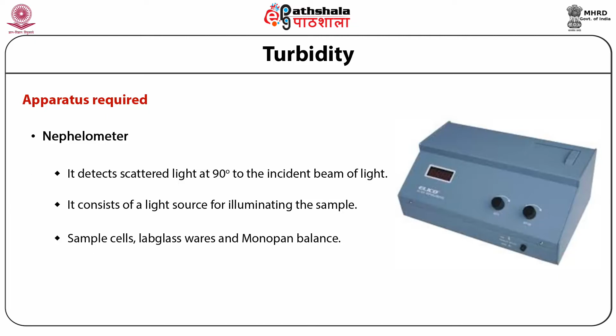The working principle of nephelometric measurement is based on the comparison of the intensity of light scattered by the sample with the intensity of light scattered by a standard reference suspension, generally a formazine polymer, under similar conditions. The reagents required for this are distilled water and stock primary formazine suspension.